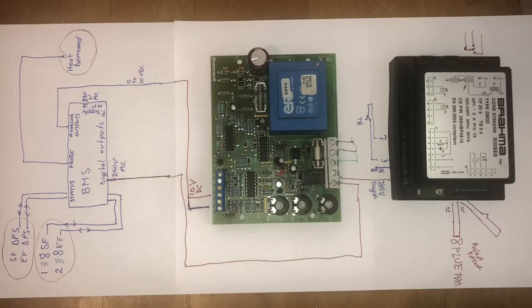If I speak for a classic environment, you can have in series with the signal hold the safety equipment, fire alarm, safety switch, all kind of protective gadgets you want to put into the system. I won't recommend doing this on the thermostat. I'd rather have it on a main power supply. So this is it so far.